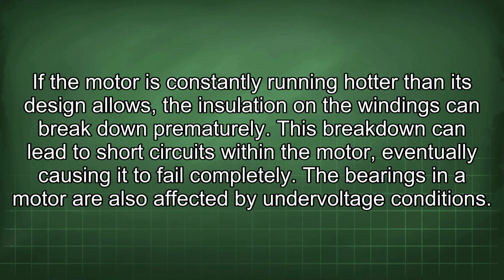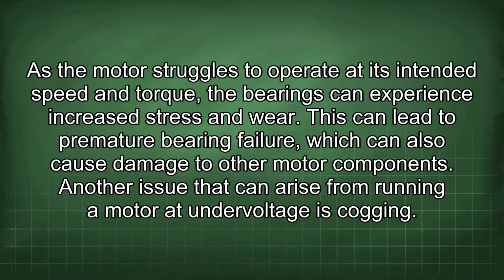The bearings in a motor are also affected by undervoltage conditions. As the motor struggles to operate at its intended speed and torque, the bearings can experience increased stress and wear. This can lead to premature bearing failure, which can also cause damage to other motor components.